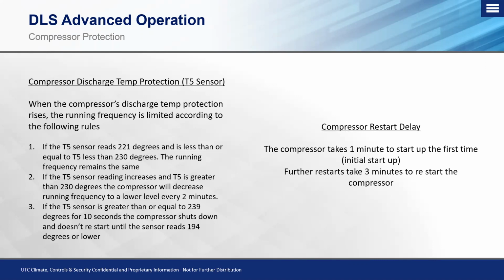Another common question that I get is, what is the delay on the compressors? So the compressor restart delay has 2 rules on there. The compressor takes 1 minute to start up from the first time, or the initial startup. Further restarts take 3 minutes. So we have a 3-minute delay before the compressor is going to restart.